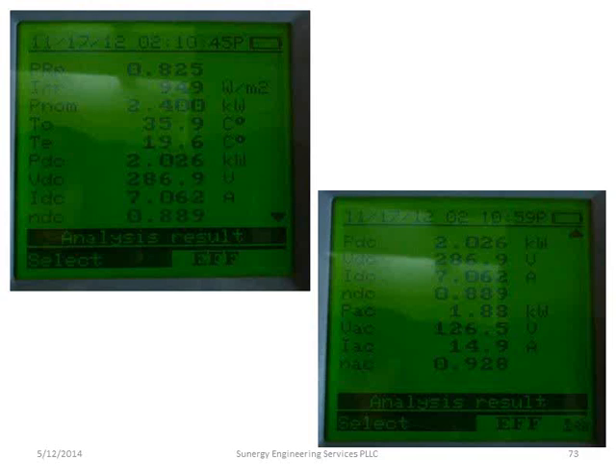So when we look at the output of the inverter, it's totally pegged. It's supposed to be an 1800 watt inverter, and it's at 1.88, so totally pegged out. It tells you the voltage of the AC and the current coming out of it, and gives an efficiency of 0.92, which is kind of low for that inverter. Anybody know why there's such a discrepancy here?